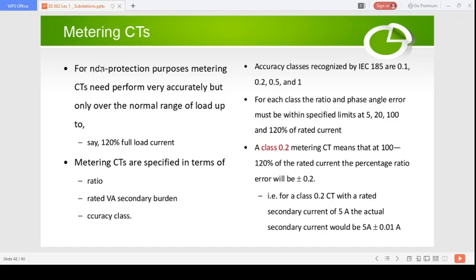Okay, so let's take a look at the metering CTs, or the measurement CTs. These are for non-protection purposes, that means basically for measuring purposes. These metering CTs need to perform very accurately, but only over the normal range of the load. So the measurement should be very accurate, but limited only to the normal range of the load, for example up to 120% of full load current. In that range the measurement should be very accurate.